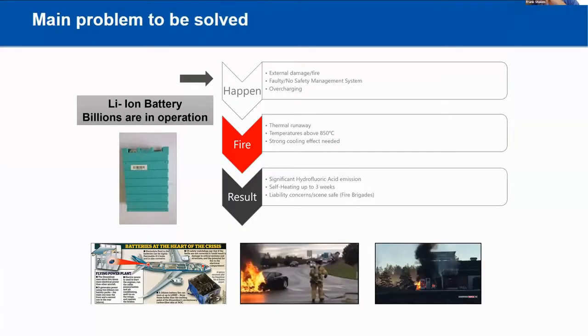So we're looking here at, what's the main problem to be solved, and what's happened? External damage or fire, a faulty or no safety management system, batteries overcharging. The result is fire from thermal runaway. Your temperatures are above 850 degrees centigrade. You need a strong cooling effect. We've shown where there's a multitude of these extinguishers that are not effective. The result is a significant hydrofluoric acid emission. Self-heating of these batteries can last up to 3 weeks. Then there are the liability concerns and scene safety with the fire brigade: exposure to your personnel, exposure to the citizens, exposure to the environment.